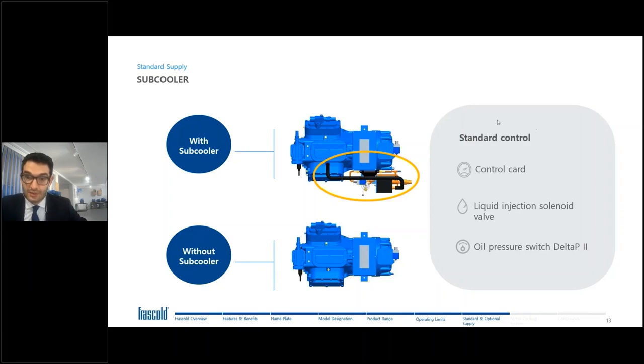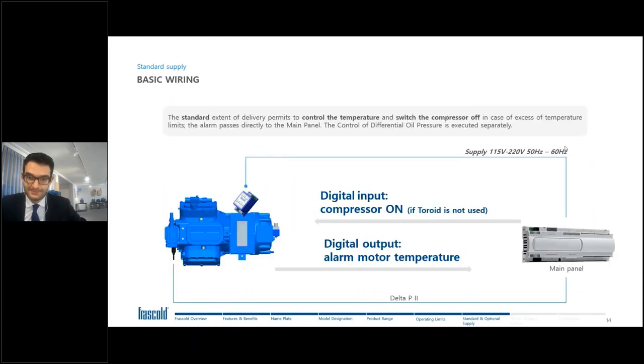In the standard control, there is also, inside the electrical box, a control card. We will see it in depth in the next slides. The liquid injection solenoid valve is the one mounted on the flange, well visible in both drawings totally at the right, mounted on the motor flange, and the oil pressure switch, the delta P2, checks that the oil pump is working correctly.